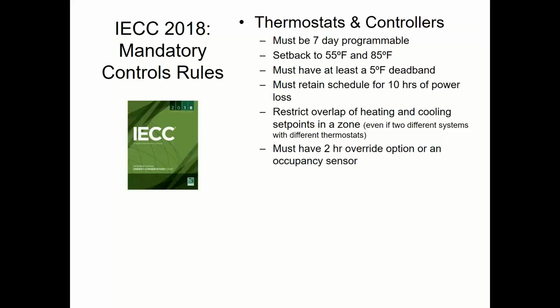You must have at least a 5-degree deadband between the heating and cooling set point. That means if your heating set point is 70, your cooling set point needs to be 75 or higher. You cannot make them closer. People do it all the time. They have to do it all the time because their system's oversized. They need to dehumidify, but it's not allowed by any of the codes. You can't have overlapping set points.